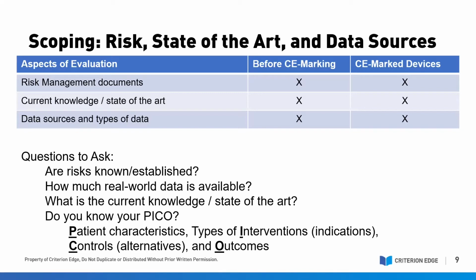The need for clinical investigations depends on the ability of the existing data to adequately address the benefit risk profile, the claims, and the side effects in order to comply with the applicable essential requirements. So if you're trying to decide if additional clinical investigations need to be carried out, you should perform a detailed gap analysis, and that overlaps quite well with your SOA section. The gap analysis should determine whether the existing data are sufficient to verify that your device is in conformity with the essential requirements pertaining to clinical performance and clinical safety.